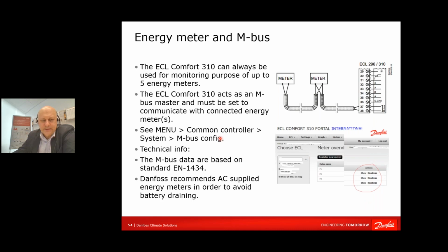You can read meters. Normally, we say that you might connect up to 5 meters to ECL, because you can have an overview of them on the display. In reality, you can connect a little bit more M-bus devices to ECL. The limit is how much power ECL can generate. So we are confident with 5 M-bus devices or meters connected to ECL. Some are connecting even more.